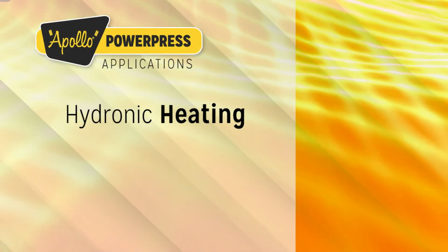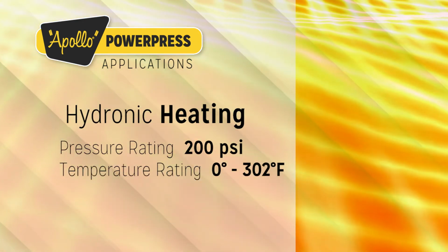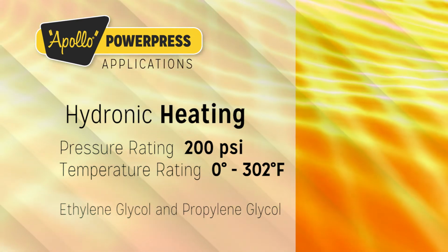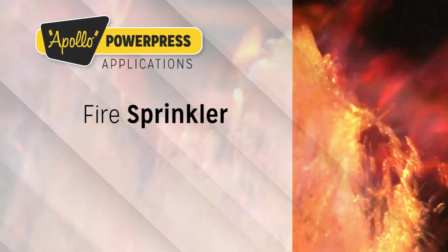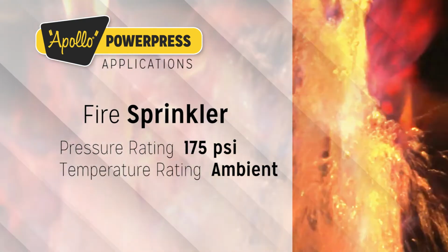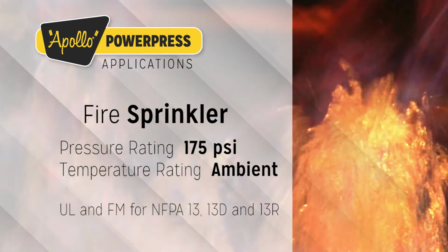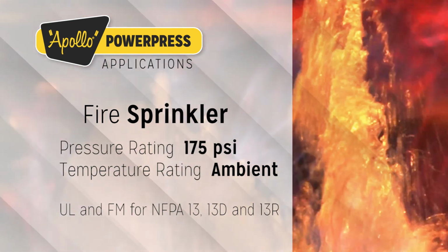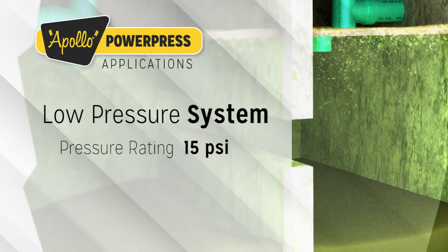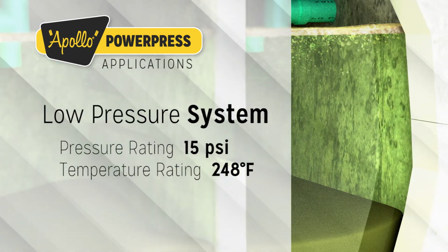Hydronic heating is rated at 200 psi and can operate between 0 degrees and 302 degrees Fahrenheit. Ethylene and propylene glycol are approved. Fire sprinkler, rated at 175 psi, is approved at an ambient temperature, and is also compliant with UL and FM for NFPA 13, 13D, and 13R. Low pressure system, rated up to 15 psi and has a max temperature of 248 degrees Fahrenheit.